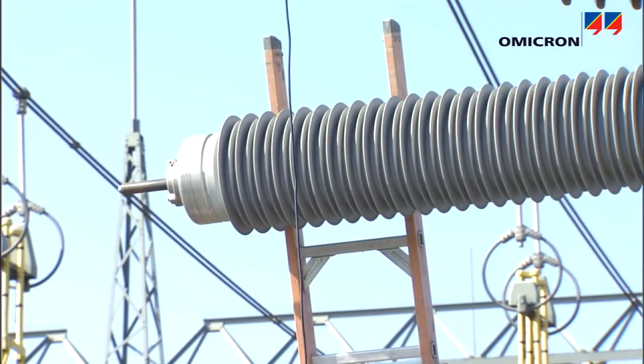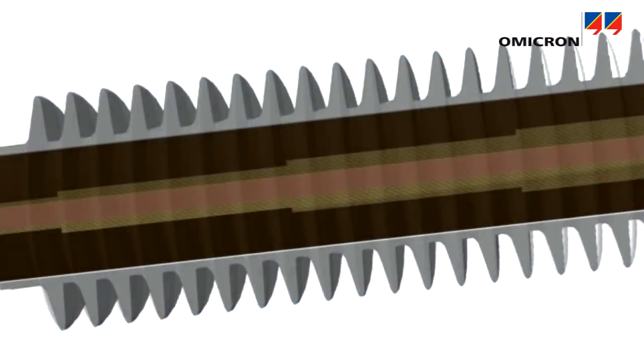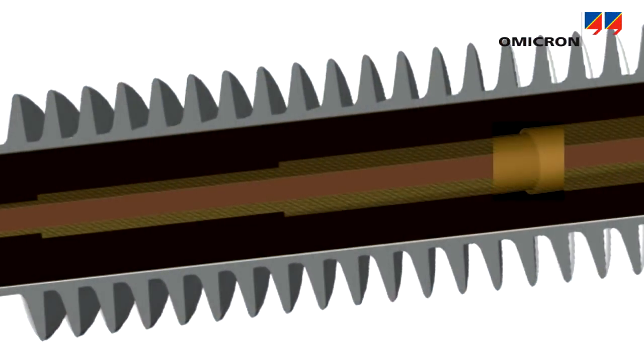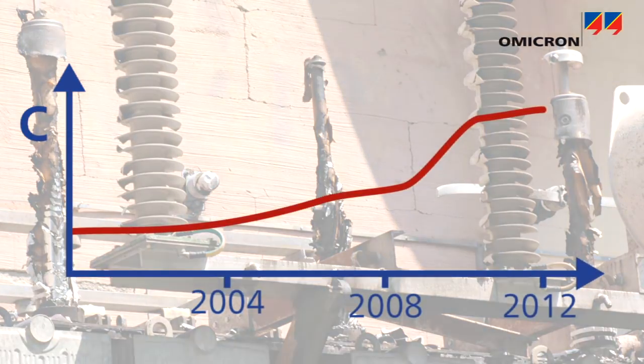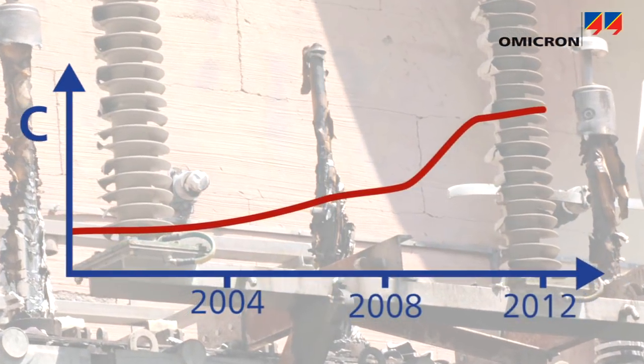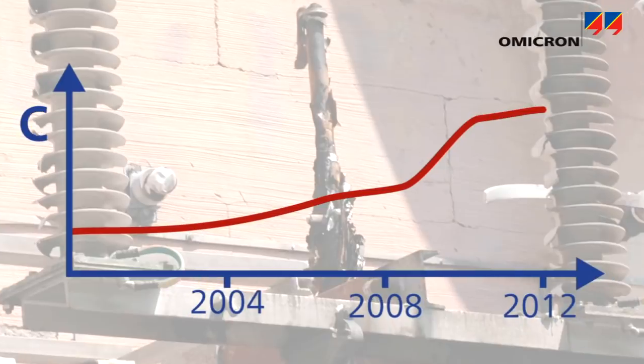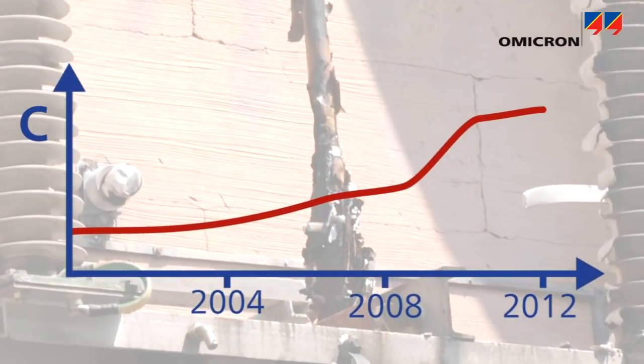Capacitance values of bushings show if there have been breakdowns between capacitive layers. A rise in capacitance of more than 10% is normally considered dangerous.